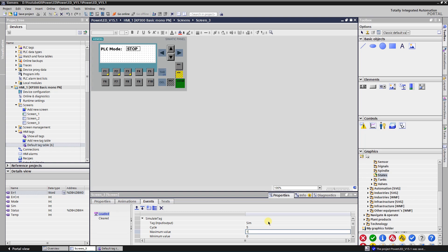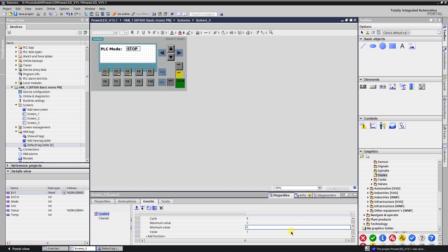Let's set Maximum Value to 1. Parameter Minimum Value is the value that the tag can assume during simulation as minimum. When the value of the tag reaches the maximum value, it will drop to minimum on the next cycle. Let's set Minimum Value to 0. Parameter Value is the value by which the value of the tag is changed during every cycle. A positive value will increment the value of the tag; a negative value will decrement it. Let's set it to 1. This setup means that the value of the tag will be changed between 0 and 1, by a step of 1, on an interval of 1 second.